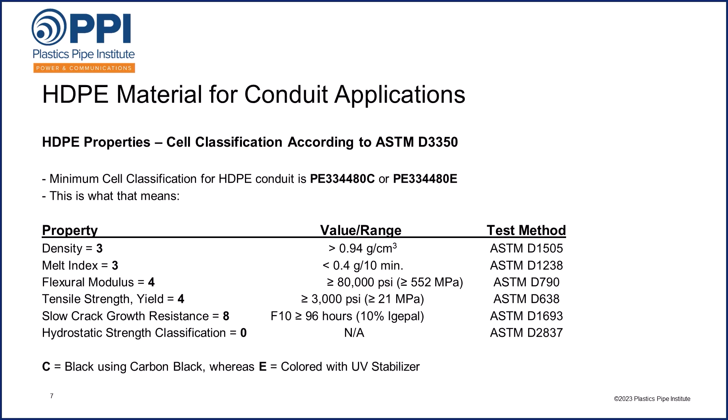The first digit refers to density, the second to melt index, the third to flexural modulus, the fourth to tensile strength at yield, the fifth to slow crack growth resistance, and the sixth and final digit refers to the hydrostatic strength classification. Conduit uses a 0 for the sixth digit, as this is exclusively for use with pressure pipe materials. Finally, the letters C or E are added at the end and refer to how UV resistance is achieved. C refers to the use of carbon black in a black product, and E refers to products which are colored with UV stabilizers built into the compound.